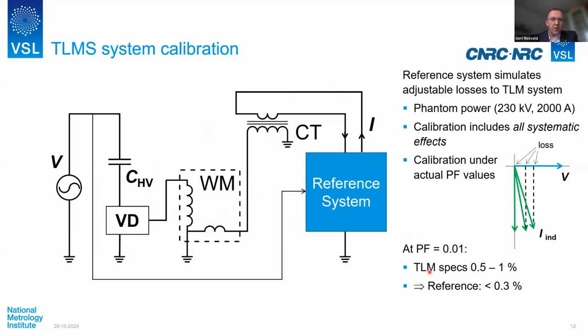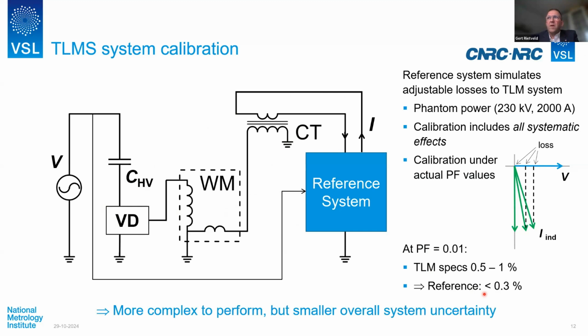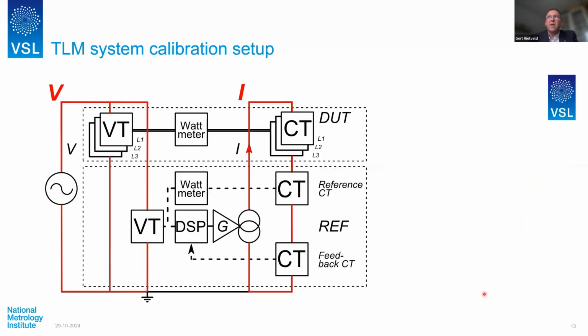So if you want to make a sensible calibration, you need to be at least, again, 3 times better. So that's where the reference should be, at the level of 0.3%, in order to make a sensible calibration. So again, the advantage: it's more complex to perform than individual component calibration, but it does lead to a smaller overall system uncertainty. So how does it work in practice?